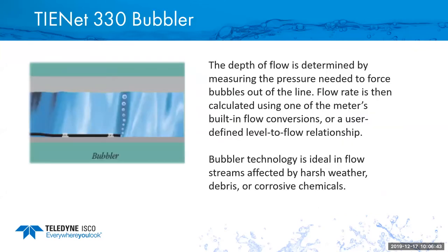Now the 330 bubbler is great in those applications that we talked about before where there's foam or wind or steam, because the bubbler is installed in a stainless steel bubble tube or a bubble tube in the flow that measures the depth of the water using the pressure that it pushes back on the bubbles. This is ideal where you've got more harsh weather, debris, or corrosive chemicals in the flow, because you're not using a sensor that's actually submerged in the flow. You're using just the bubbles of the air that are pushing out.